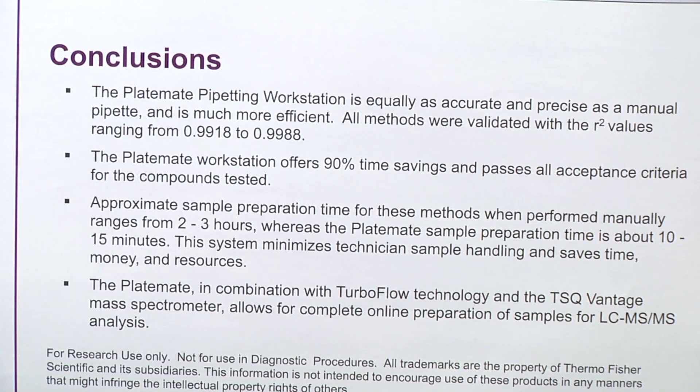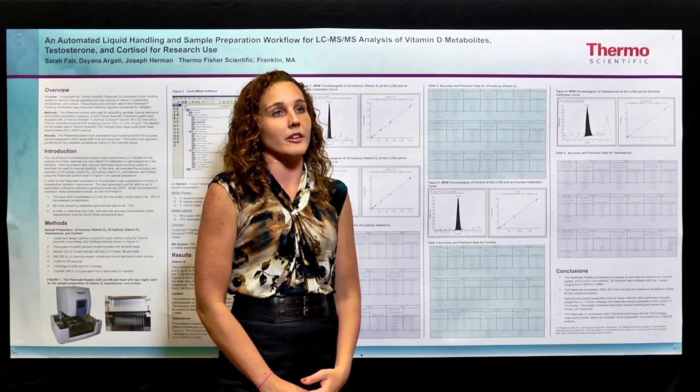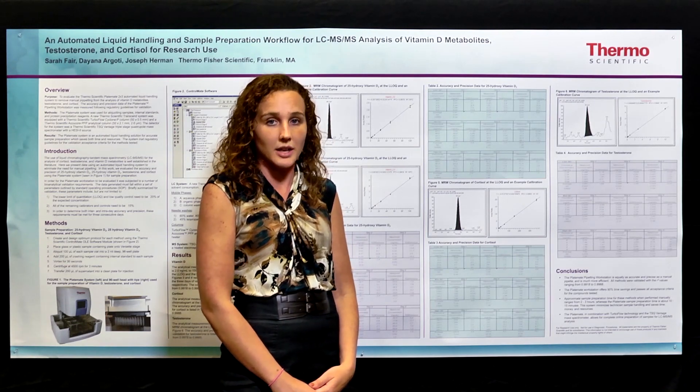In conclusion, the Platemate Pipetting Workstation is equally as accurate and precise as manual pipetting, but saves much more time — approximately 90% time savings. To put this into comparison to manual pipetting, before I had to do 2 to 3 hours of prep, but now I only need to do 10 to 15 minutes.